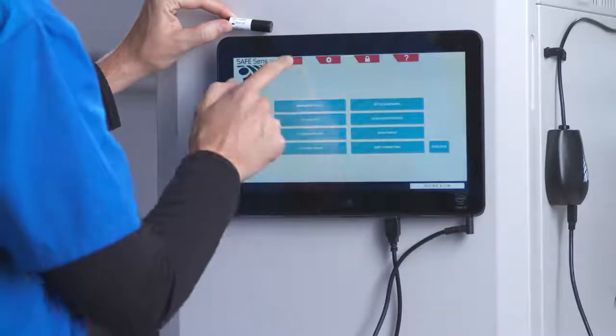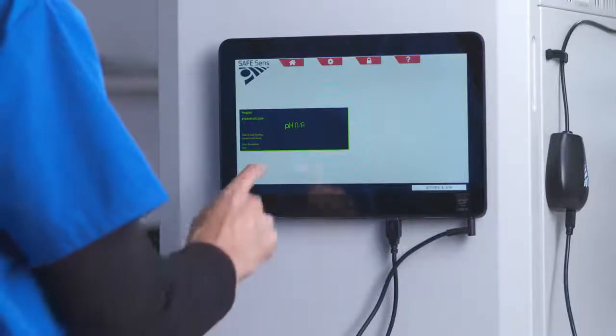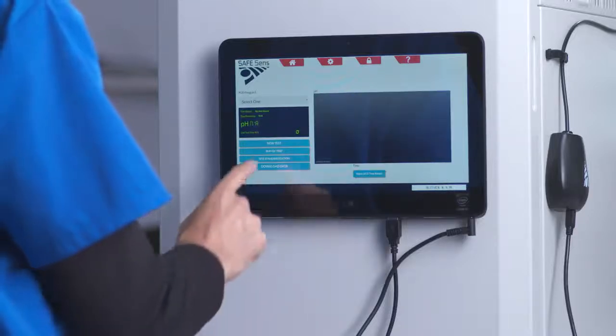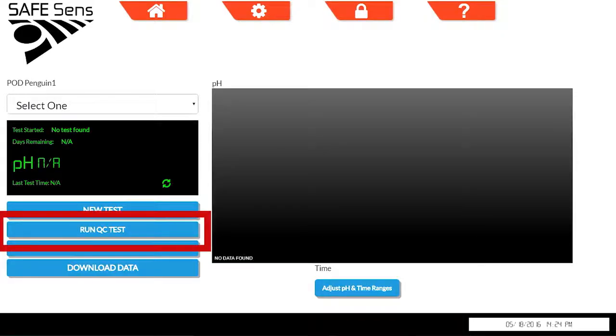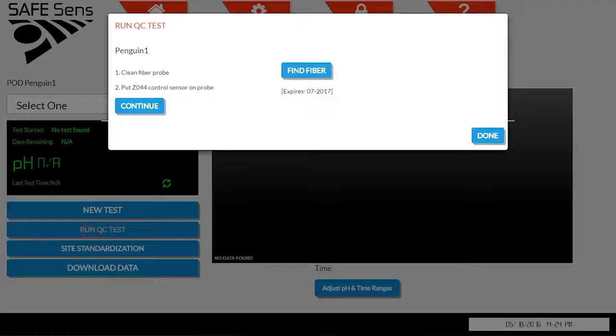Run a QC test on each TrakPod after it has been installed in your incubator. Also run the QC test once a week when changing your pH sensor. To run the QC test, select the TrakPod you will test, then use the Run QC Test button. If you are not sure which TrakPod or fiber optic you are testing, press the Find Fiber button to cause the TrakPod's fiber to blink 3 times.